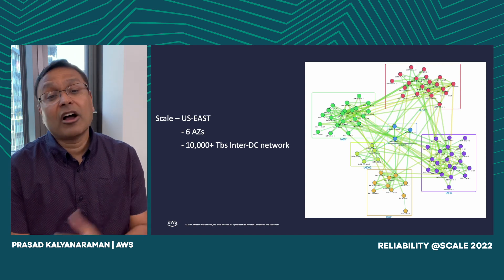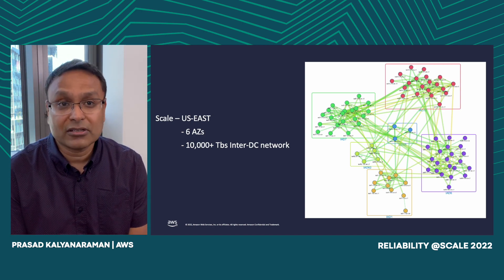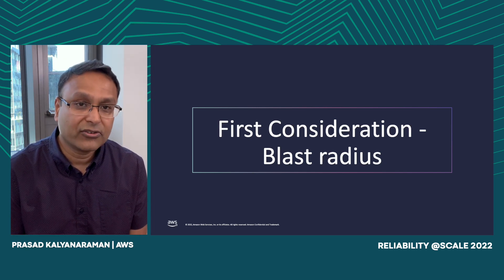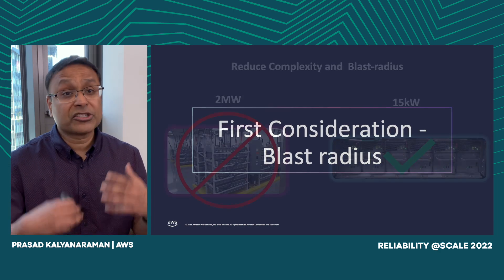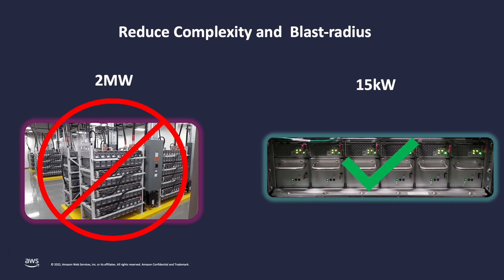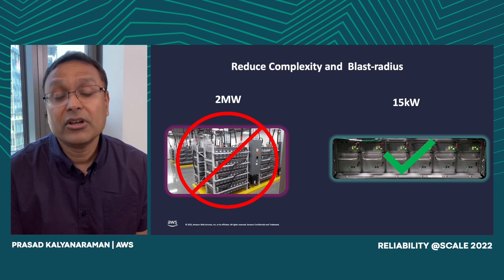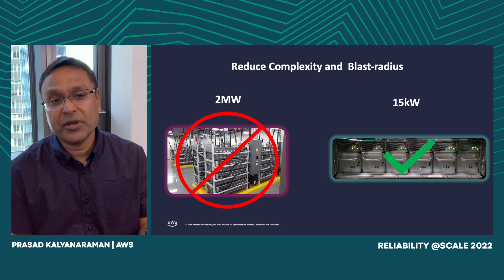When you operate at this scale, the first important thing for resiliency is to make sure your blast radius is much smaller. If you think about our evolution of data center design, our initial data centers were built with UPSs where each UPS was servicing a lineup of about two megawatts. A lineup for us is a UPS plus a generator combination — about 70 or so racks powered by a single lineup of utility plus UPS plus generator.